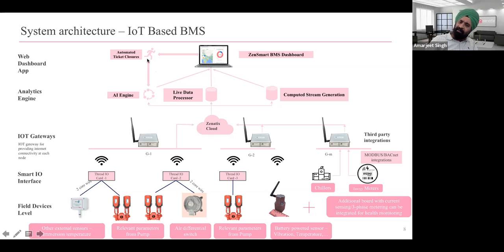People don't need to infer that data; those data points are inferred by automated algorithms that keep improving as they get more data, and they create tickets. These tickets have actionable insights rather than just saying there's little cooling in a specific area. The ticket may actually say there's little cooling because the air filter is blocked, or because the valve is stuck and not operating, or because the VFD is stuck at 30 hertz, etc.